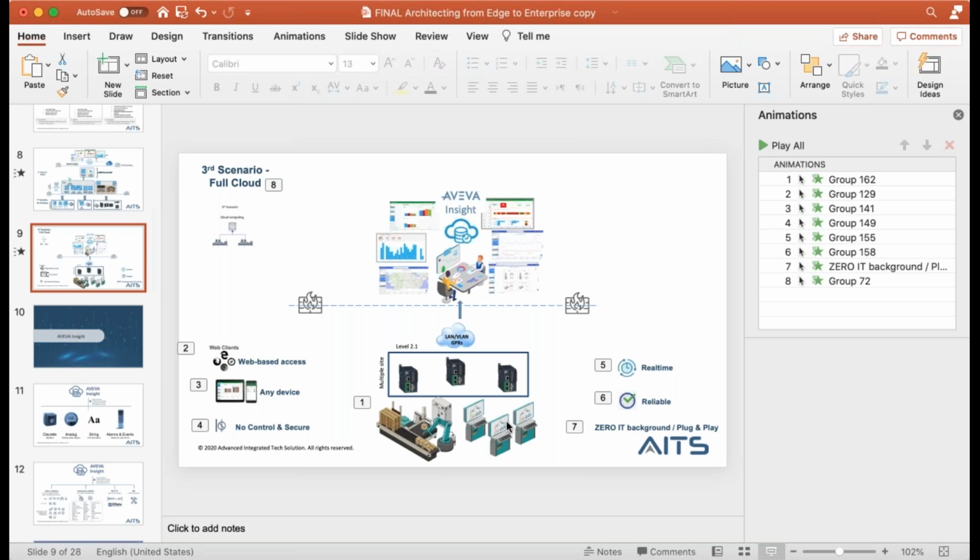The gateway will connect with the PLC, maybe via Modbus or different types of protocols, and then we will decide what tags you need to push from the PLC, and the push will happen from that gateway controller. This gateway controller will push the data into a predefined access, that's also concerning the username, the access and the cloud address, and this is how you can push the data directly from the PLC without having a local HMI there.